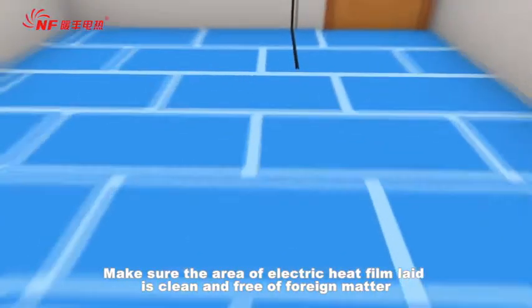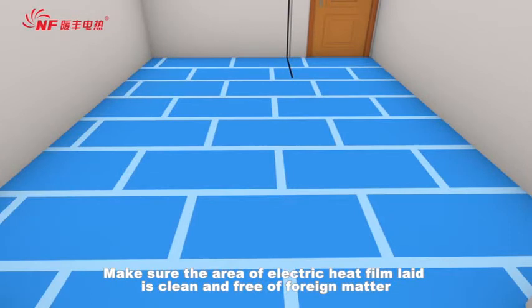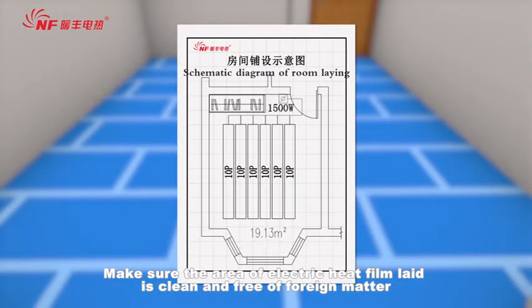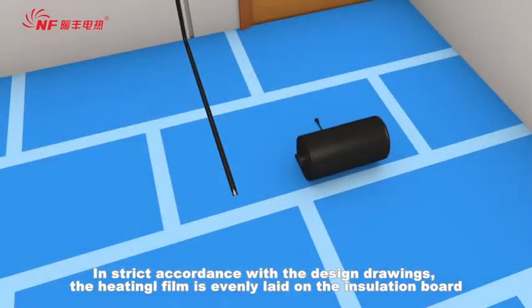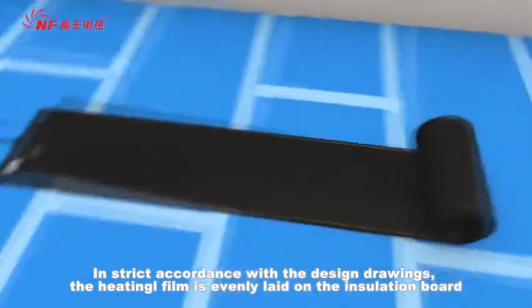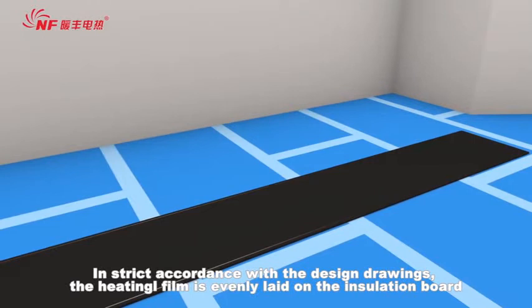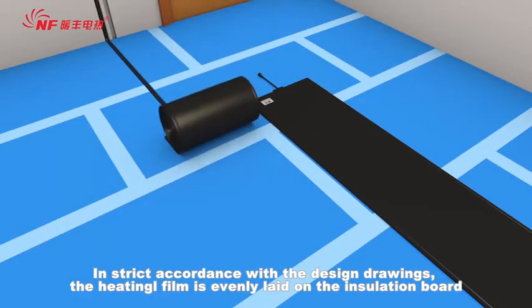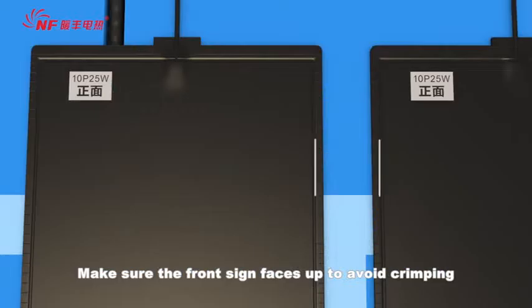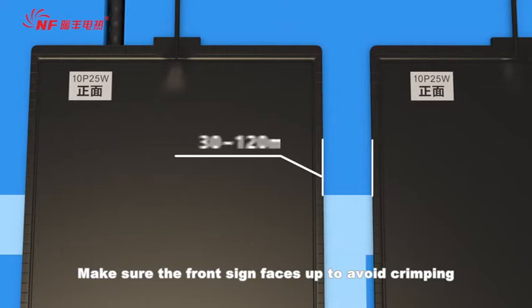Make sure the area of electric heat film laid is clean and free of foreign matter, in strict accordance with the design drawings. The heating film is evenly laid on the insulation board. Make sure the front side faces up to avoid cracking.